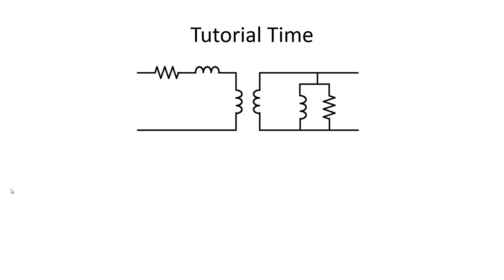Let me draw the equivalent model of the transformer. There we have an ideal transformer with a nominal ratio of 20,000 to 480. The short circuit resistance and short circuit reactance are on the high voltage side. On the low voltage side, we have the equivalent core loss resistor and the magnetization reactance.